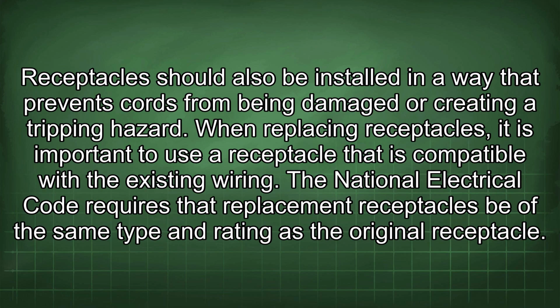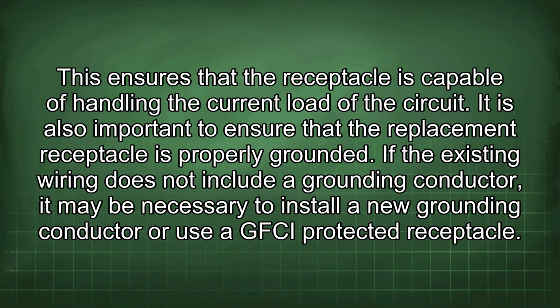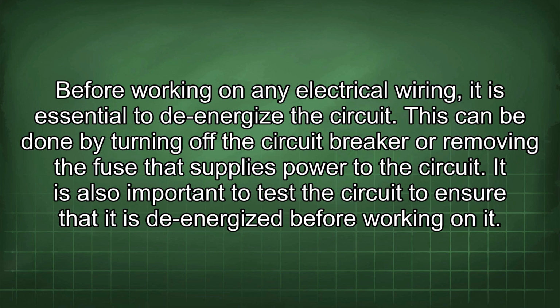When replacing receptacles, it is important to use a receptacle that is compatible with the existing wiring. The National Electrical Code requires that replacement receptacles be of the same type and rating as the original receptacle. This ensures that the receptacle is capable of handling the current load of the circuit. It is also important to ensure that the replacement receptacle is properly grounded. If the existing wiring does not include a grounding conductor, it may be necessary to install a new grounding conductor or use a GFCI protected receptacle.